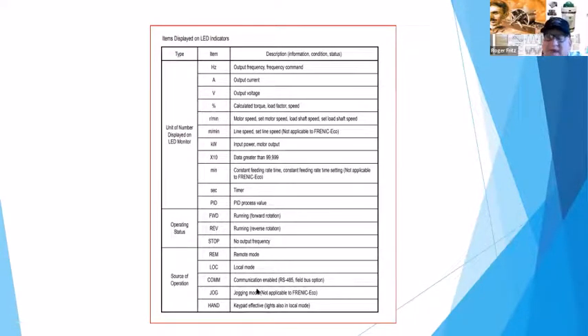But I always like to go back to my simplicity part of it, because all we're really doing is controlling the frequency. We're controlling the output voltage amount as we're giving it the frequency, which then controls the amperage going out to the motor, which you have to keep in tolerance. The motor has a nameplate with the recommended current flow. At that current flow, it's normally at a certain speed, so it has enough airflow across it to keep it cool. It's normally got revolutions per minute, RPM, your minimum speed, and your kilowatts, which tells what the output power is. It also shows whether you're running, reverse, forward, local or remote operation.